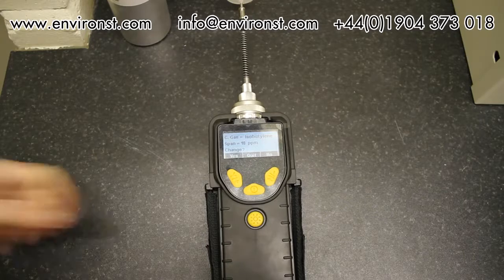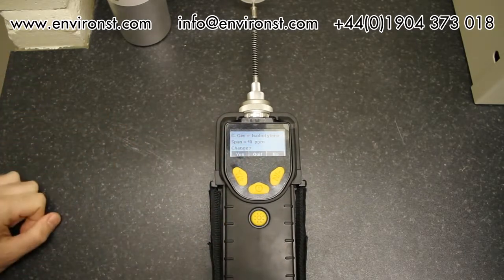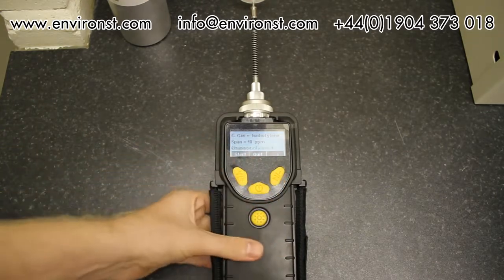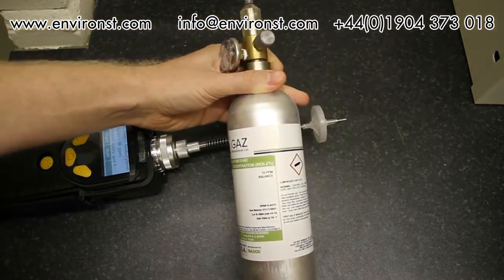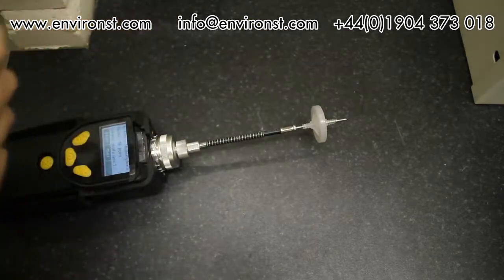Now instead of 100 ppm isobutylene, you can see here that it's actually 10 ppm isobutylene. So for ppb level instruments, we always calibrate with 10 ppm. So it asks me, do I want to change that value? I'm going to say no. I have my 10 ppm isobutylene here. I'm going to turn that on.